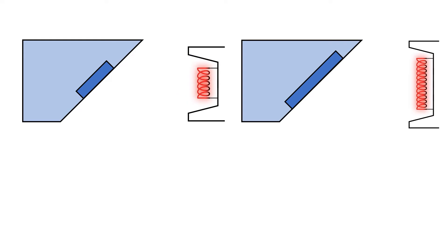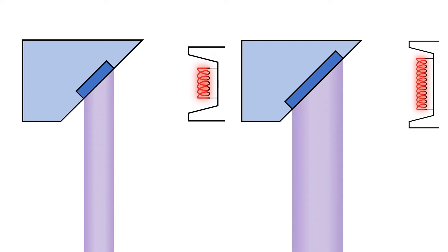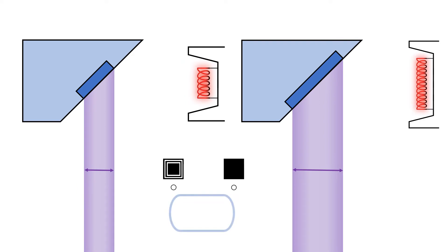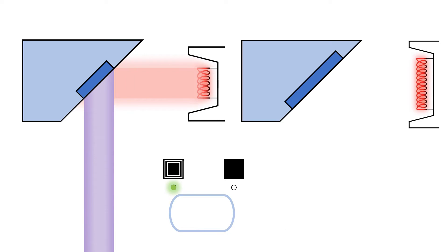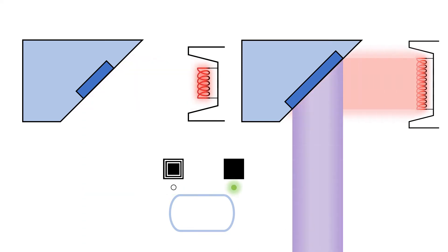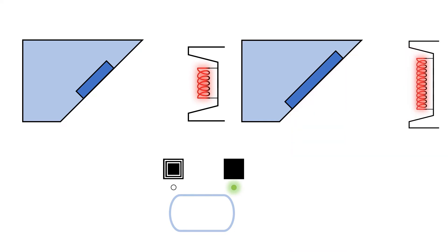On the left is an x-ray tube using a small filament and on the right is an x-ray tube using a large filament. Notice how the width of the effective focal spot changes when you select the small filament versus the large filament. The smaller filament produces a smaller effective focal spot and the larger filament produces a larger effective focal spot.